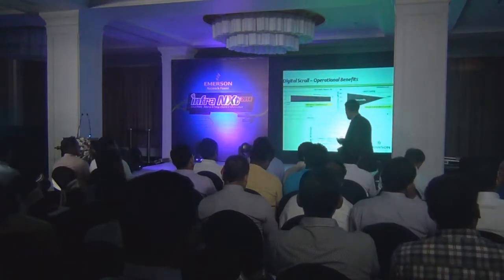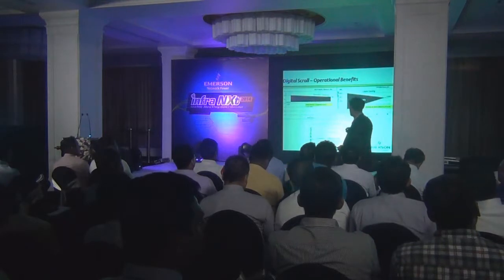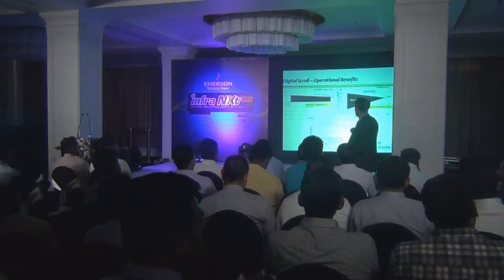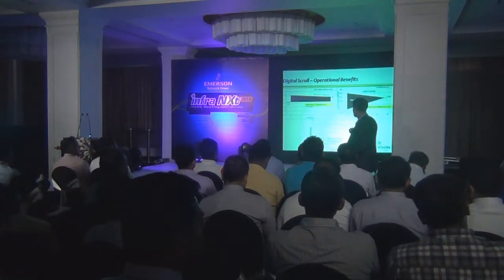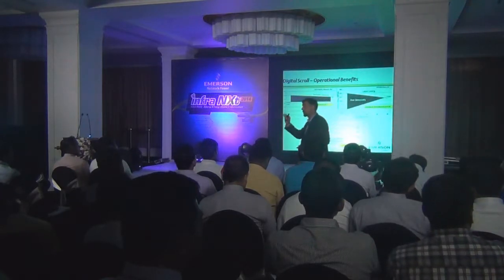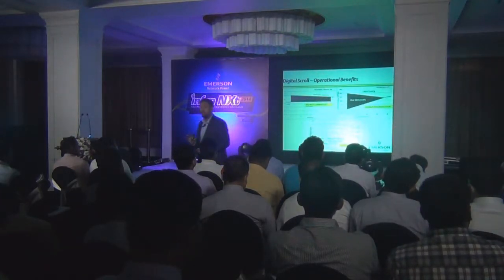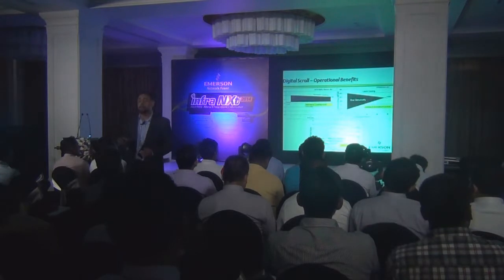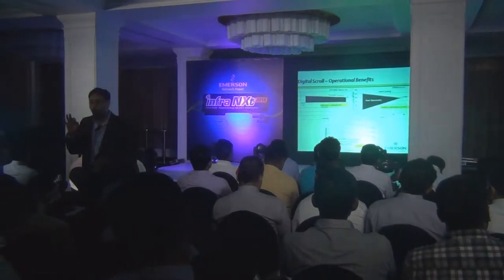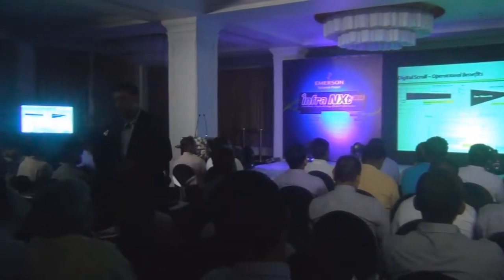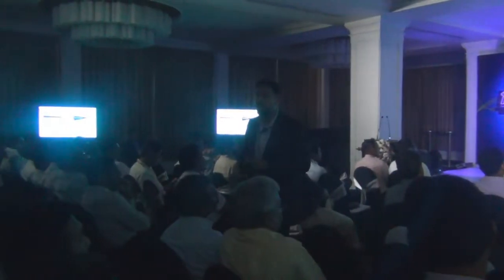This is what I was talking about, what happens exactly when the ambient goes down and your system efficiency improves. EER goes up as high as 14 EER, which is very high. 12 EER is what you use if you want to go for even a gold certified building with a digital scroll system. 12 EER is considered for such purposes. We are talking about 14. We are talking much beyond it.